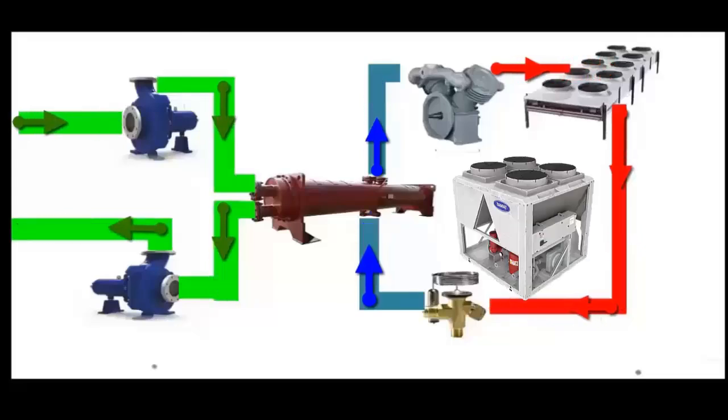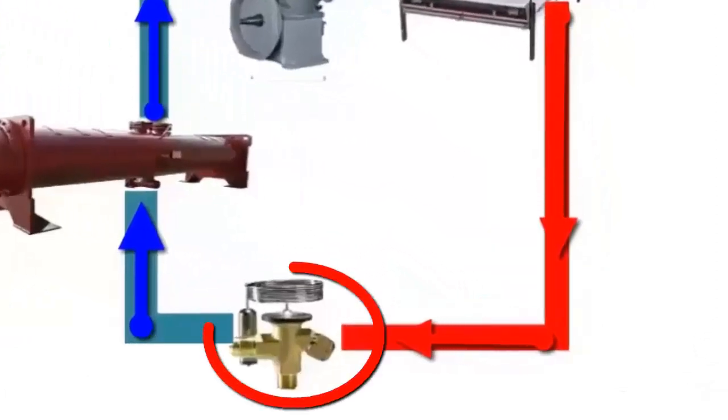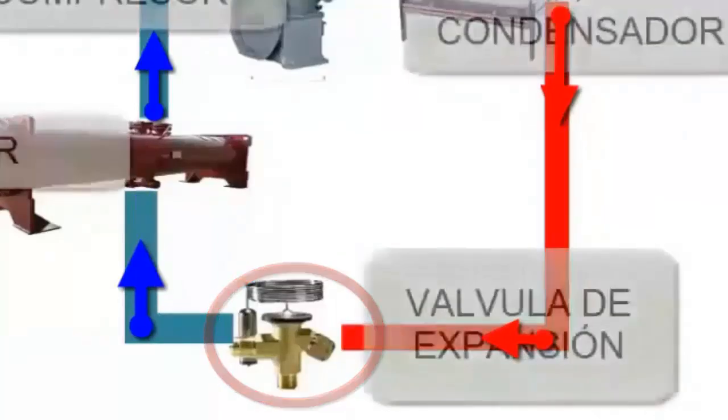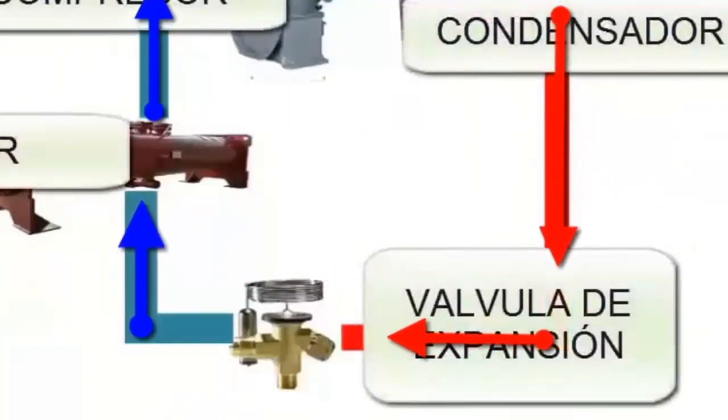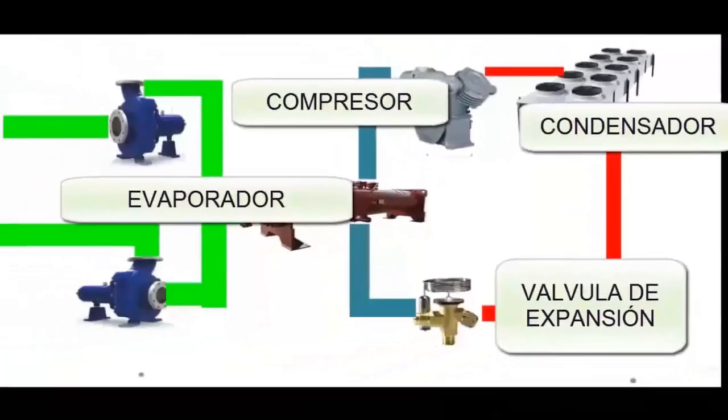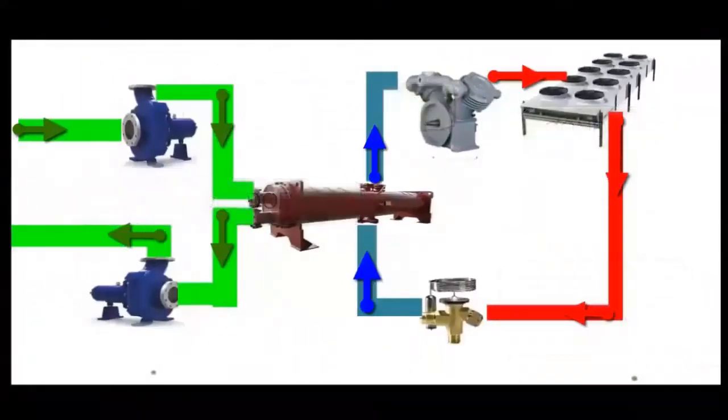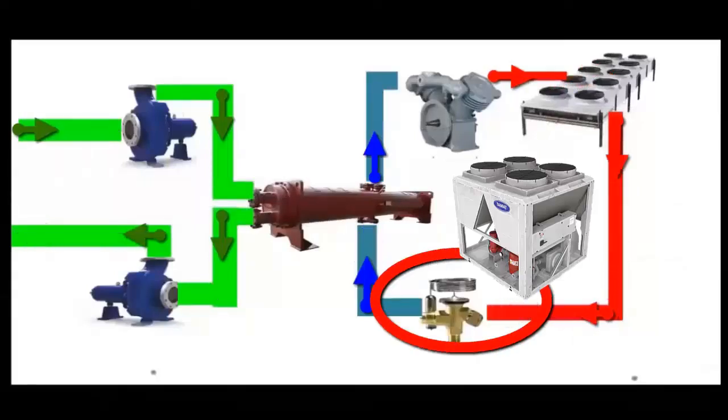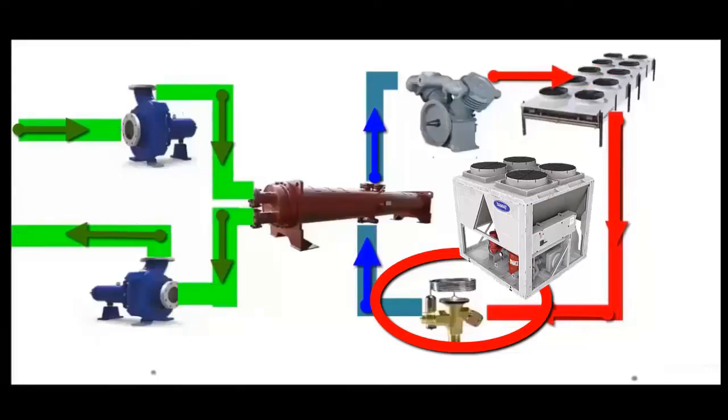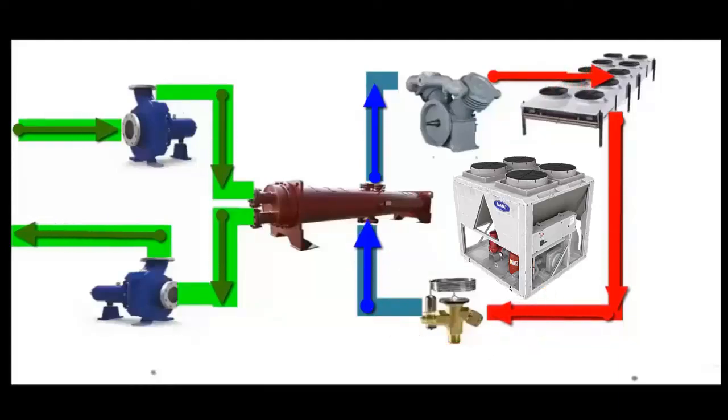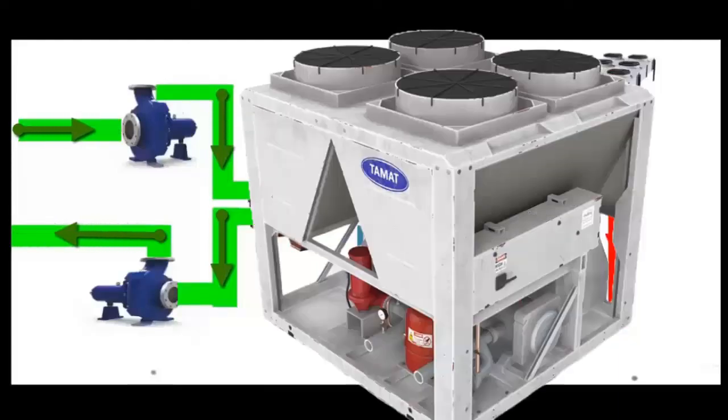After passing through the condenser, the refrigerant, now in a high pressure liquid state, is directed to the expansion valve. This valve functions to reduce the pressure and temperature of the refrigerant, preparing it to re-enter the evaporator. The pressure reduction in the expansion valve is crucial because it allows the refrigerant to enter the evaporator in a suitable state to absorb more heat from the water, thus restarting the cooling cycle. This cycle repeats continuously while the chiller is in operation, ensuring a constant supply of cold water for the system.